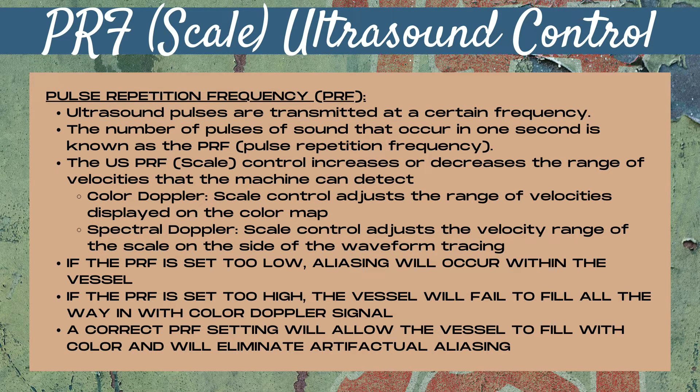The PRF is also known as the scale control on an ultrasound machine. Ultrasound pulses are transmitted at a certain frequency. The number of pulses of sound that occur in one second is known as the PRF, or pulse repetition frequency. The ultrasound PRF or scale control increases or decreases the range of velocities that the ultrasound machine can detect.